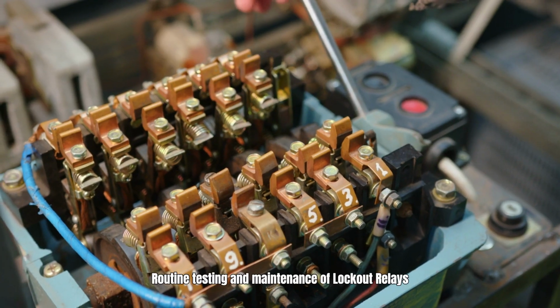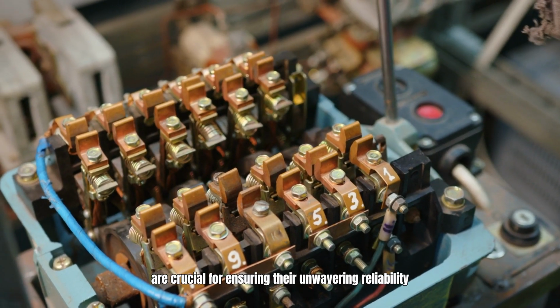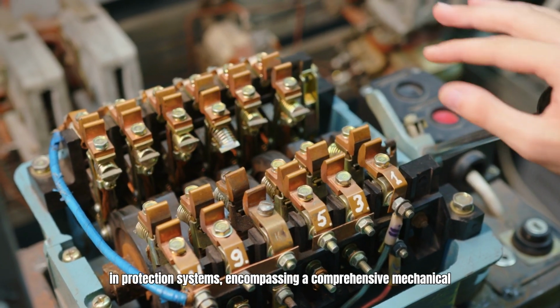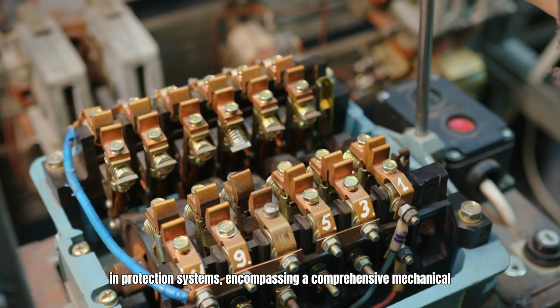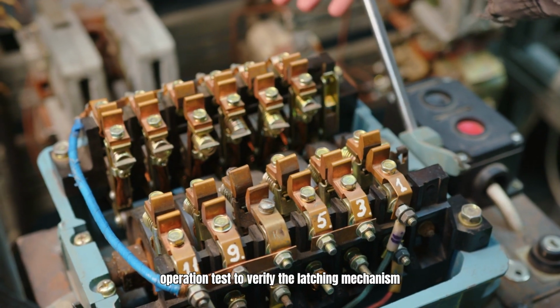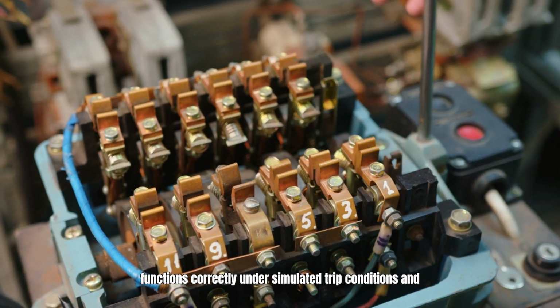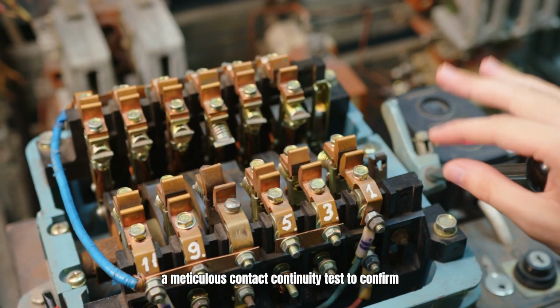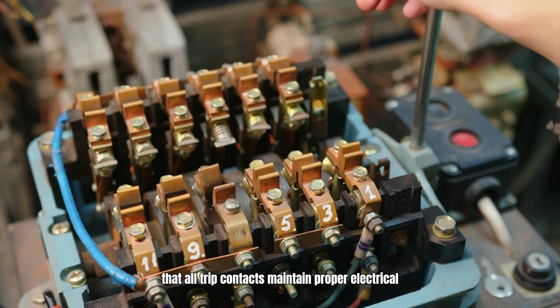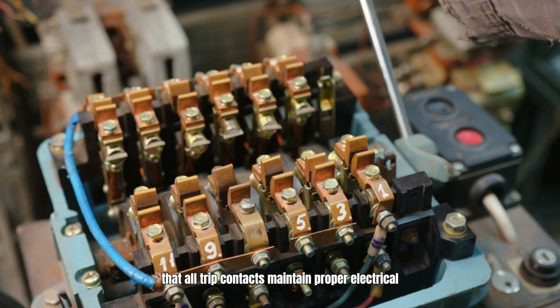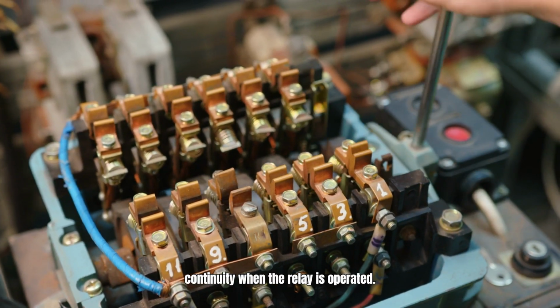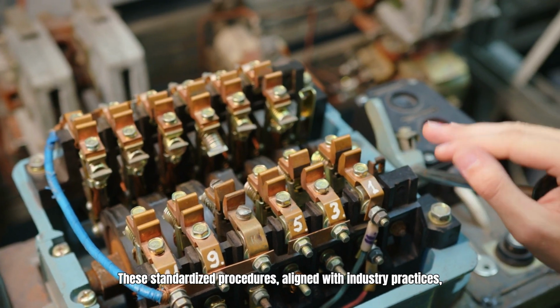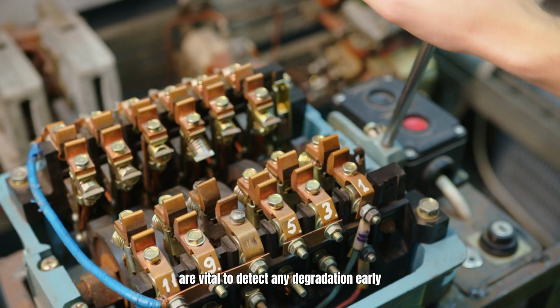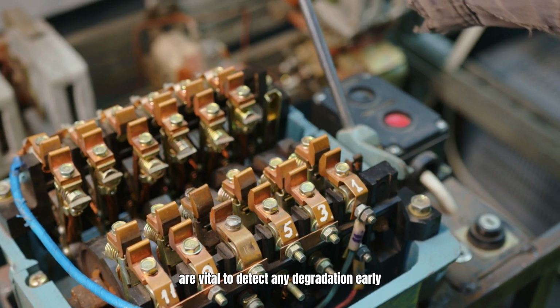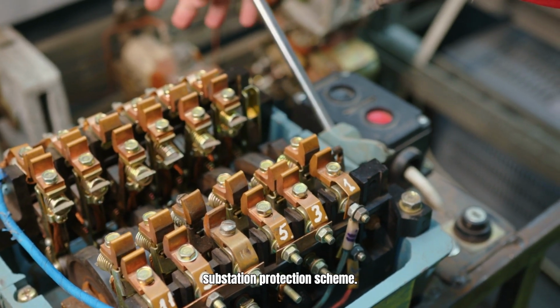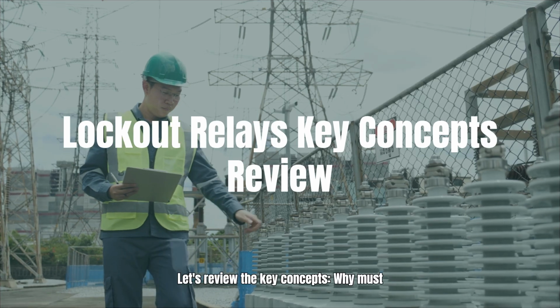Routine testing and maintenance of lockout relays are crucial for ensuring their unwavering reliability in protection systems, encompassing a comprehensive mechanical operation test to verify the latching mechanism functions correctly under simulated trip conditions, and a meticulous contact continuity test to confirm that all trip contacts maintain proper electrical continuity when the relay is operated. These standardized procedures, aligned with industry practices, are vital to detect any degradation early and uphold the integrity of the overall substation protection scheme. Let's review the key concepts.